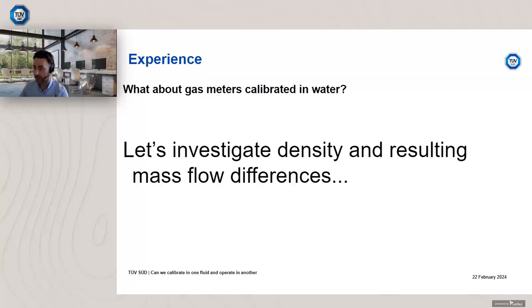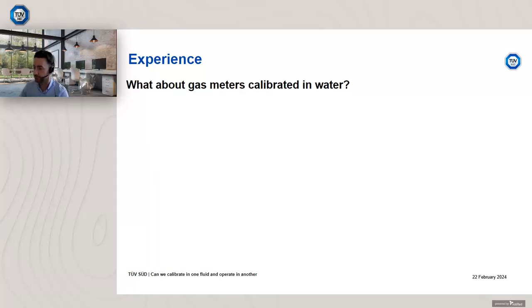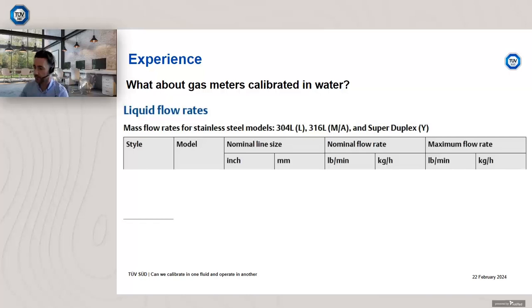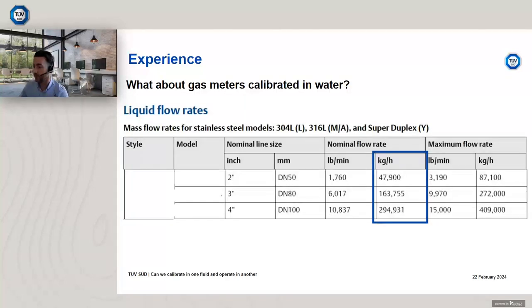That's one of the real challenges. How do you match gas calibration with a liquid when the density is so different, and as such, the mass flow is also completely different? So to illustrate this, I have a meter manufacturer's flow rates from their datasheet for a liquid device. I've blocked out the model and name, obviously don't want to share that, but just to show you the nominal line size and the nominal flow rate.